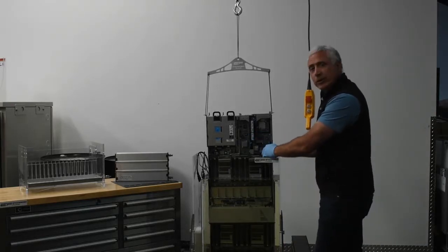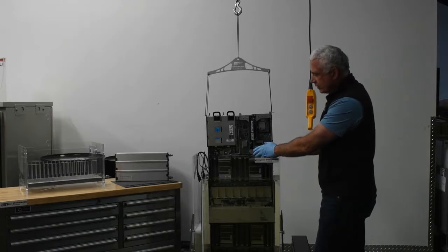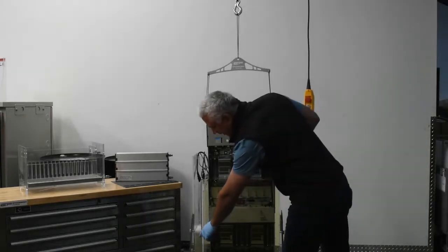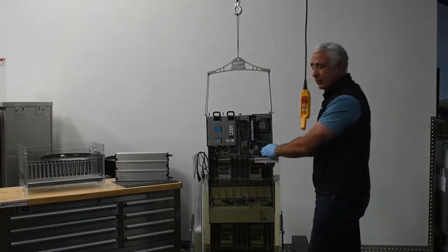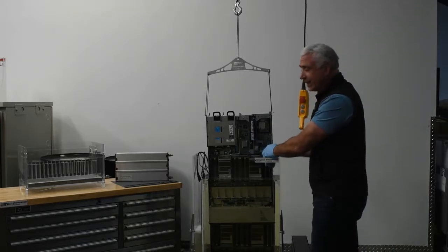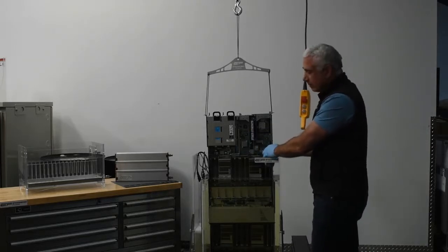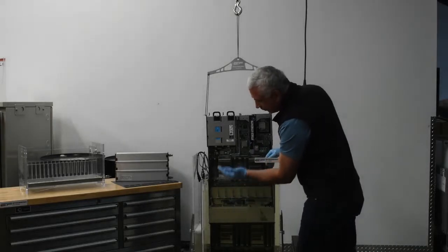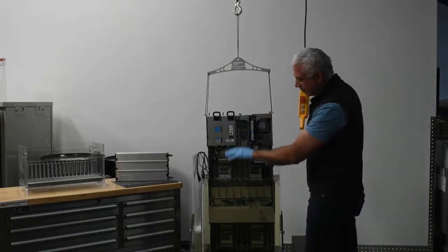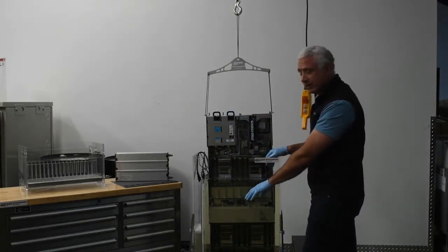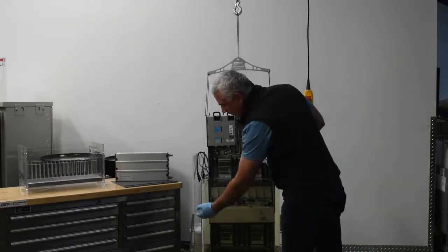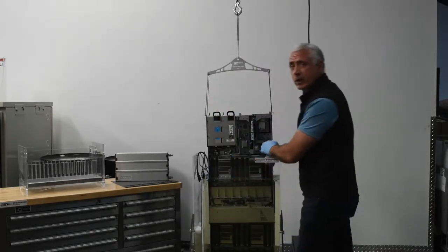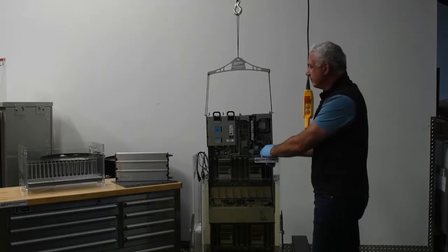I've finished doing the replacement of the memory and as you can see the displacement level of the fluid has risen as I put this back in. And again that's very important because of the design of this tank—the level is self-regulating, meaning that as I drop this server deeper into the tank it will overflow but simply fill up the recovery channel as shown here.